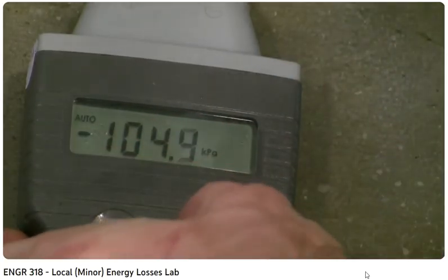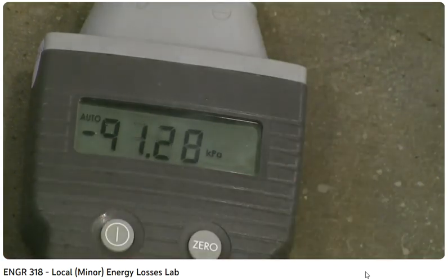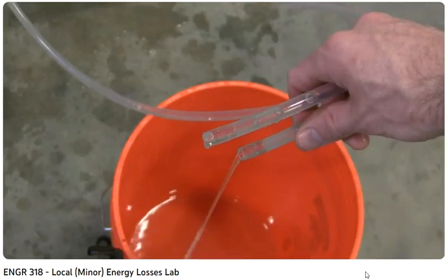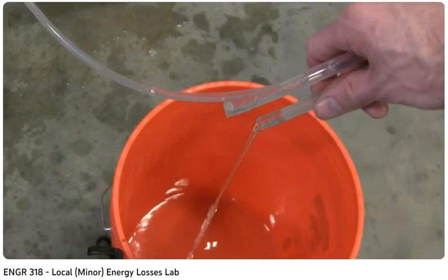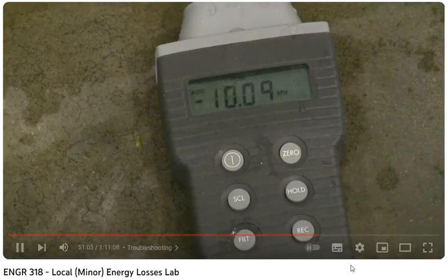Okay, fill the flow. Make sure the instrument is reading zero. All right, it is not, which may mean that once again we've got a plugged valve. So let me pause the recording and troubleshoot. Okay, only one of the tubes is leaking water. They both should be when they're taken off the pressure measuring device. So it looks like we've got some values there with which to work. Okay, I'm inspecting for air bubbles and don't see any.